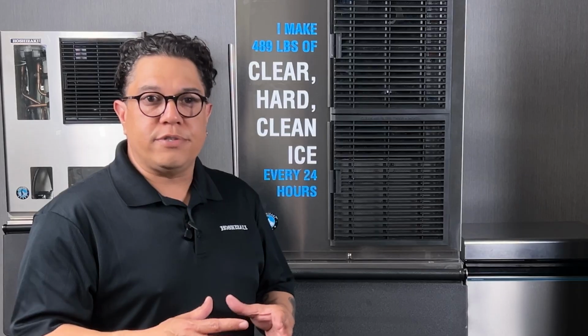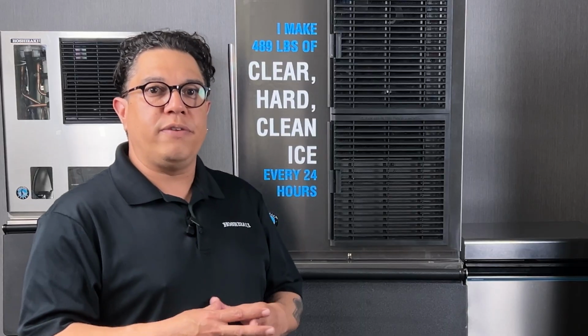Now we're going to talk about beeps number 6 and 7. There are low voltage and high voltage alarms. First, when you have this alarm, the first thing we're going to do is go straight to the K2 connector, because that's where the board gets power. We're going to confirm that we have 10.5 volts.